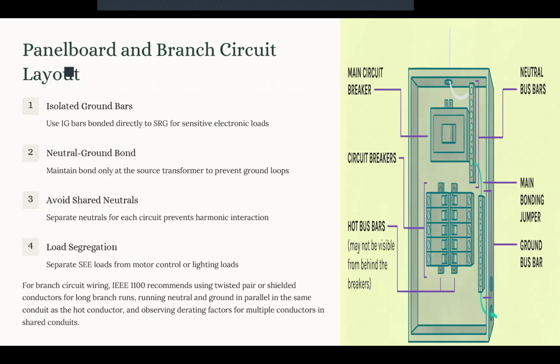Now, in our power system, in this topology, another component that we need to pay attention to when we design or choose between the options that we have is the panelboard. The purpose of choosing a proper panelboard and branch circuit design for sensitive electronic equipment is to make sure we have clean, stable, and noise-free power delivery for those sensitive electronic devices. So we can minimize the harmonic interactions, control the common mode noise, and prevent transient propagation between the loads.